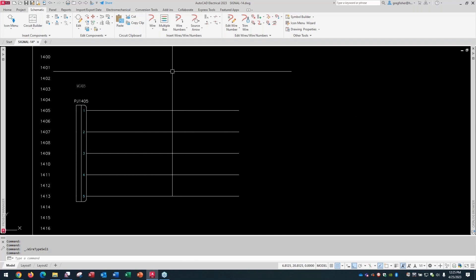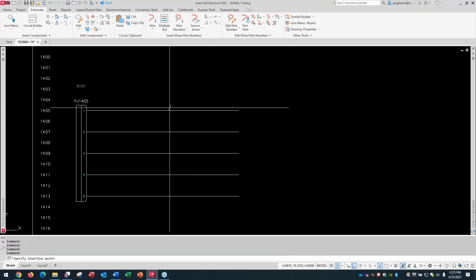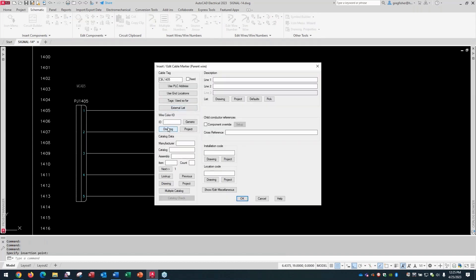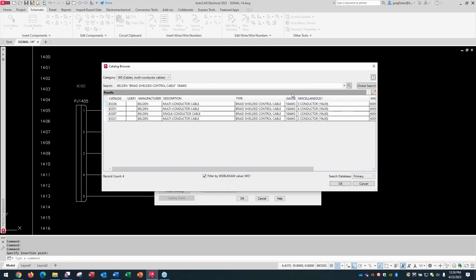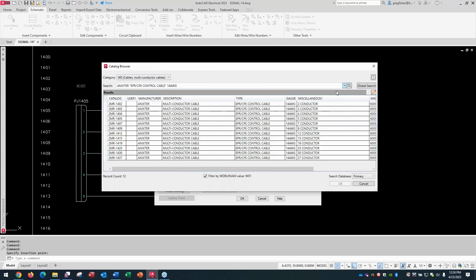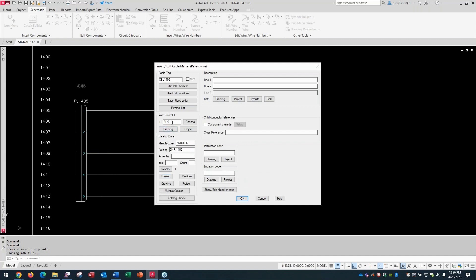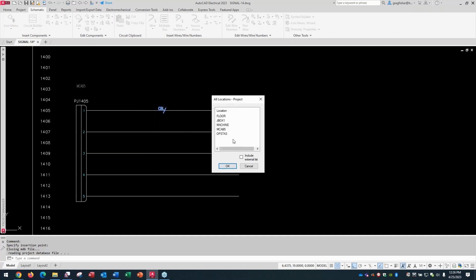And then I'm going to insert a cable. And I'll drop this down right about here. And I'm giving myself a lot of space here, as you're going to see in a minute. And I'll put a catalog number on here. I'm just going to pick a five conductor Anixter cable. And that way, it fills in the wire color ID for me. And I'll give this a location, VEMCAB as well. And I'll select OK.